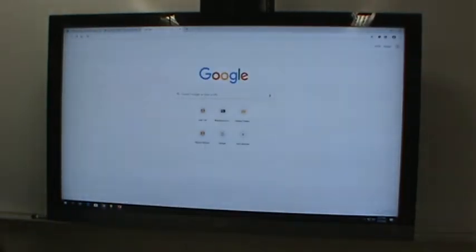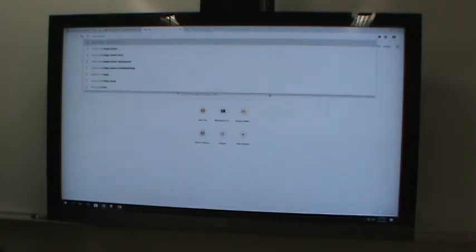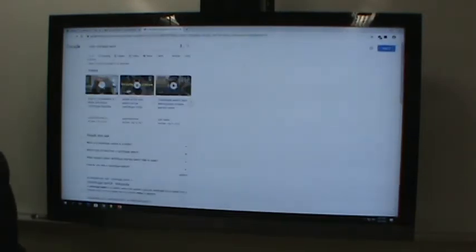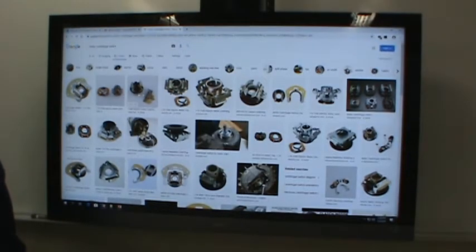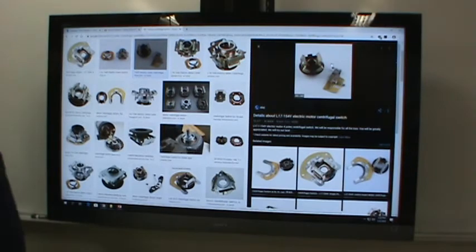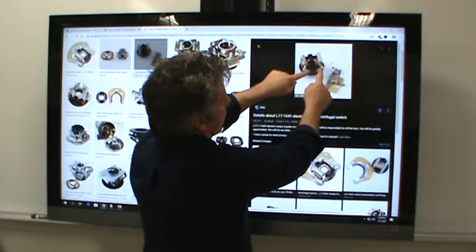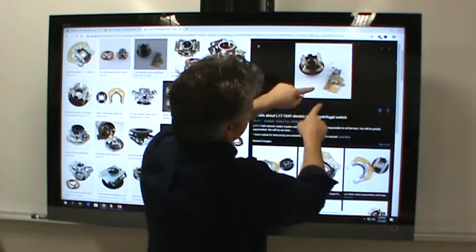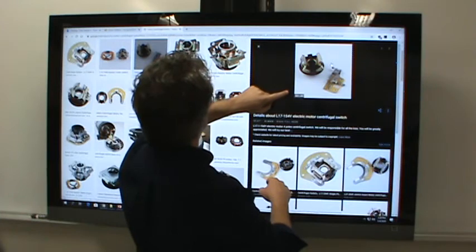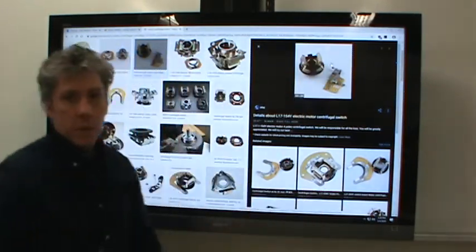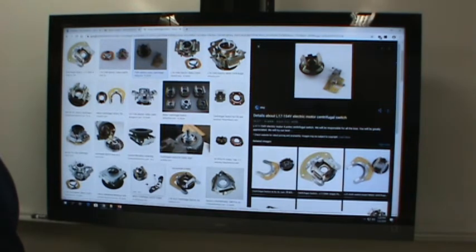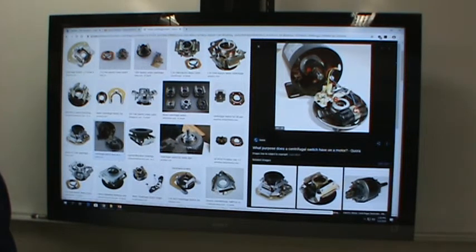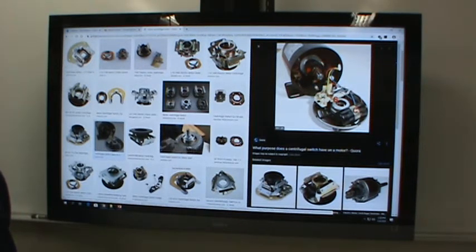Let me show you what a centrifugal switch looks like on a motor. It would be mounted on the rotor — there are springs keeping these weights in, but as they rotate the weights come out. There's another piece that pushes on a switch that turns off the start capacitor, and it's usually mounted in the back end of the motor.